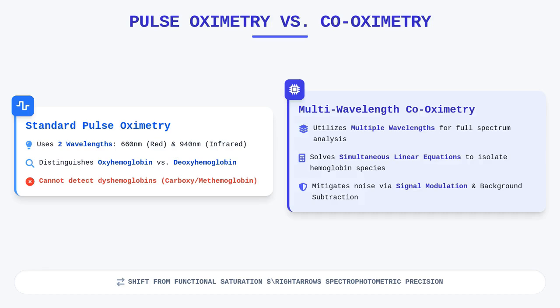Co-oximeters overcome this limitation by utilizing multiple wavelengths of light to perform spectrophotometric analysis across the entire hemoglobin absorption spectrum. By solving simultaneous linear equations derived from the absorbance data, the device mathematically isolates the concentrations of various hemoglobin species. This computational process is highly sensitive to ambient light interference, which the device mitigates through sophisticated algorithms, including signal modulation and subtraction of background noise. Effective operation of these systems requires an intimate understanding of the transducer optics and the underlying mathematical models.